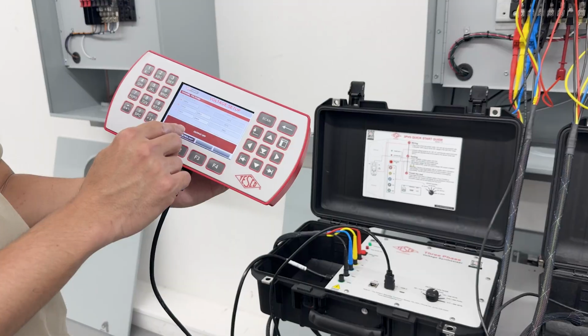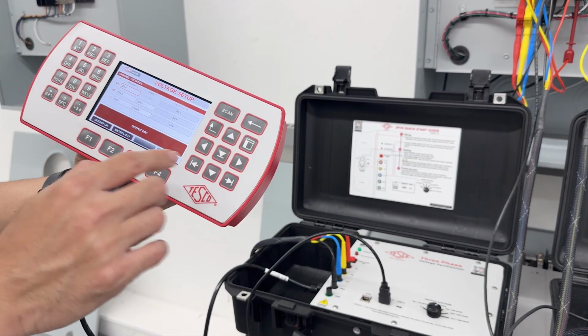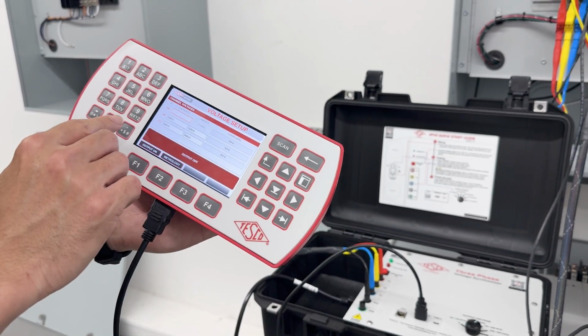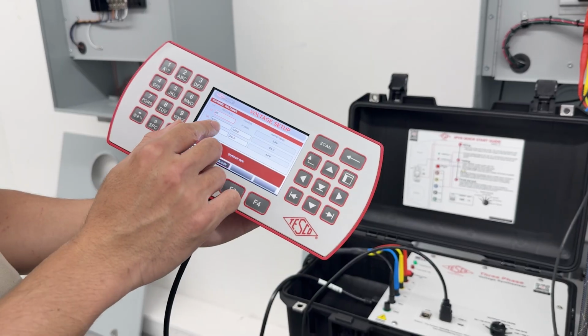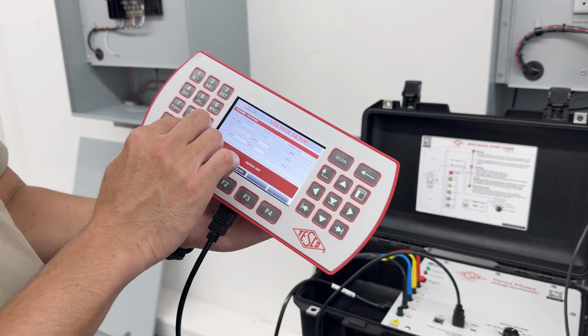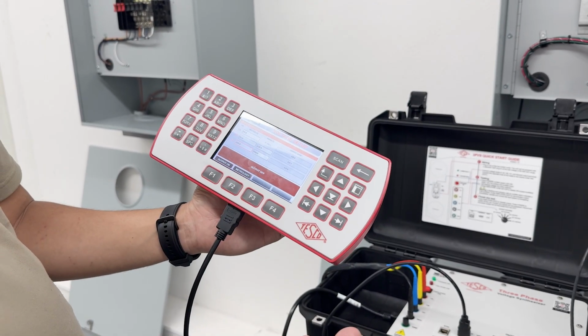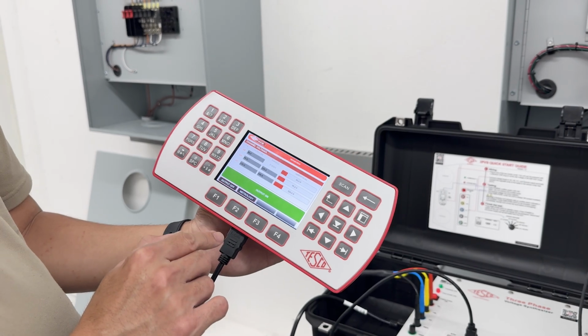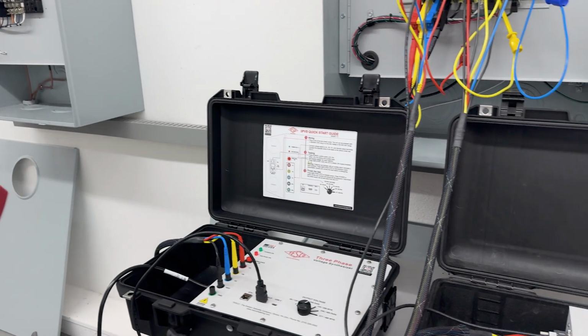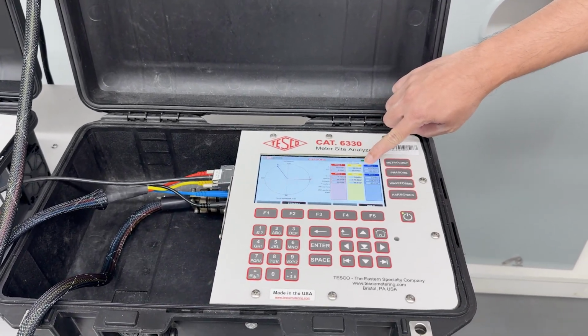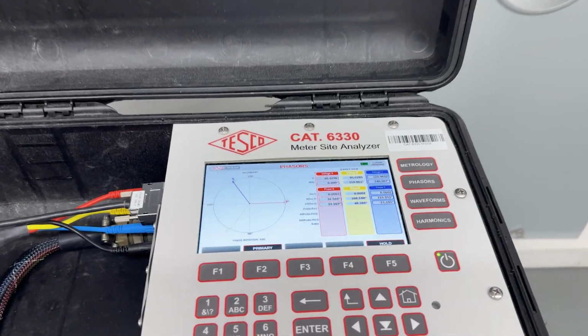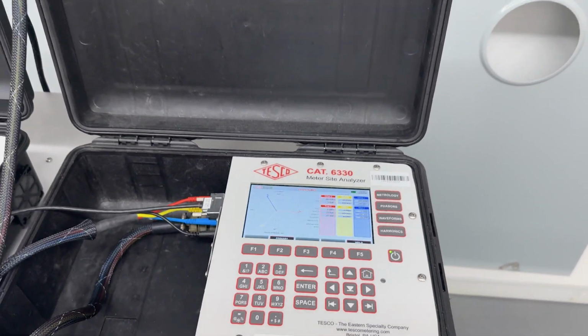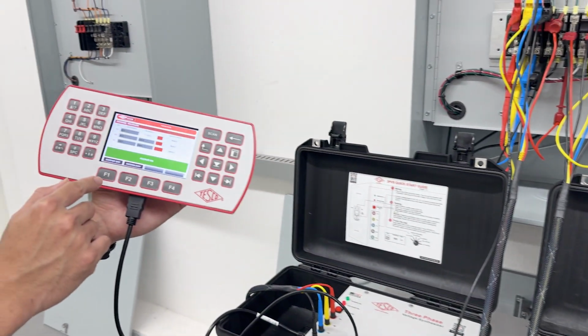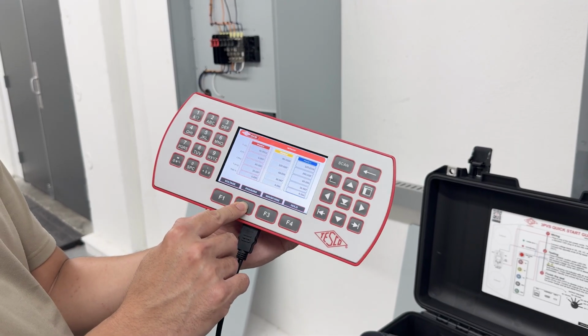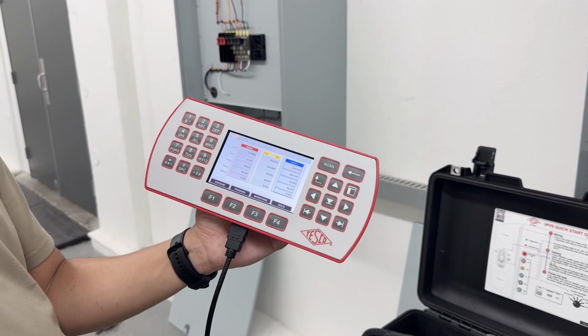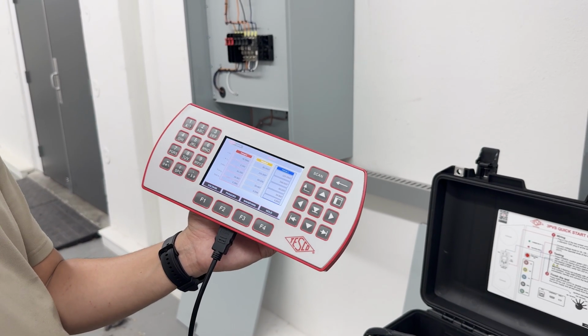Okay, so in here, it's a touch screen, so I can edit it to a specific voltage. Let's just say we want a voltage of 80 volts for VA, and on VB, let's just make a random number, 95. And then, yeah, that's it. We can turn it on. So if we click that, it's displaying voltage is active right now. And you can see in the 6330, it's reading the voltage. So it's reading 80, 95, and 120, which matches here. And in the handheld, there is a metrology section where you can see the numbers. Okay, so that's the same number that's displayed on the 6330, except the 6330 is highly accurate.